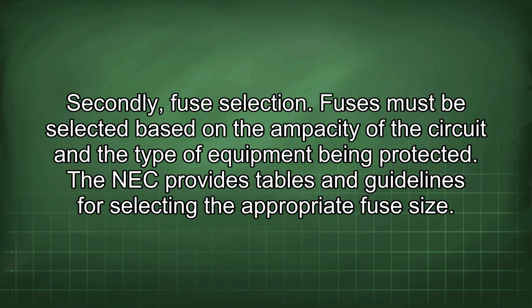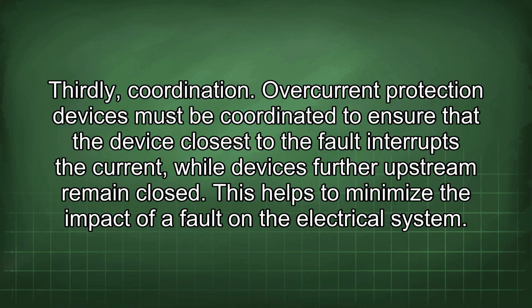Fuses must be selected based on the ampacity of the circuit and the type of equipment being protected. The NEC provides tables and guidelines for selecting the appropriate fuse size. Thirdly, coordination. Overcurrent protection devices must be coordinated to ensure that the device closest to the fault interrupts the current, while devices further upstream remain closed. This helps to minimize the impact of a fault on the electrical system.